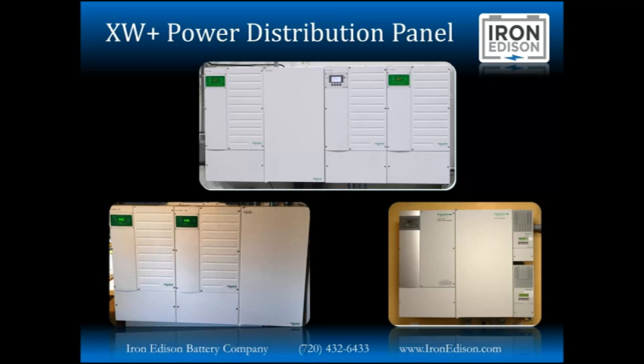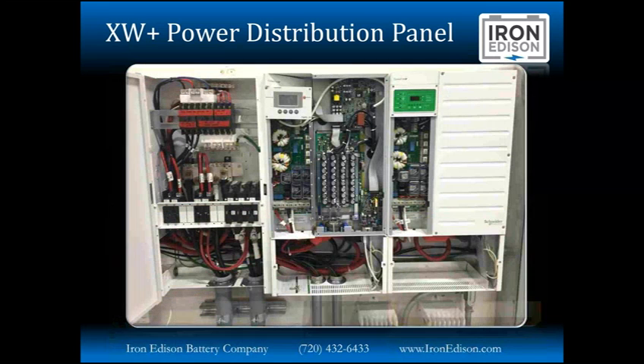inverter with a couple of the MPPT 60 charge controllers that mount right to the side of the power distribution panel. Here's a great view inside the power distribution panel on the left-hand side, as well as an inverter with both the service panel and then the main circuit board protection panel removed. We typically don't need to remove that main panel. This is just to get a view inside of the inverter. On the right-hand side, you see the inverter with the service panel removed. Typically, this is the only part that we need to take off to install all the different AC wires.